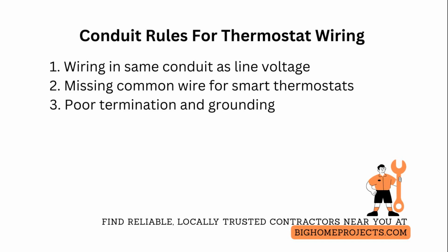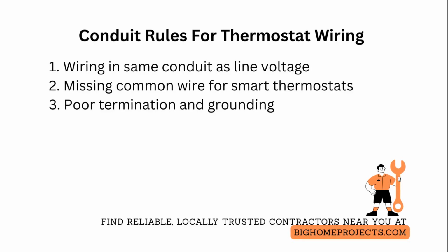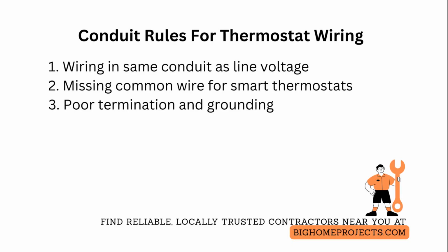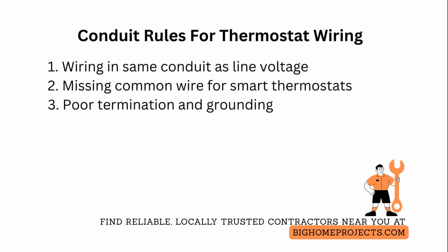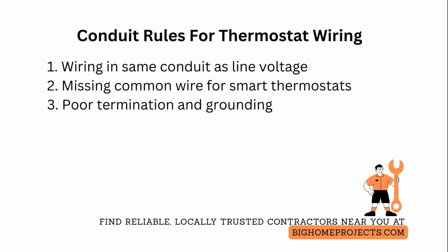The third frequent problem is poor termination and grounding, causing transformer hum and intermittent operation. Correct this with solderless, crimped, or properly torqued screw terminations, shield grounded only at one end, and using ferrules on stranded wires for reliable clamp connections.